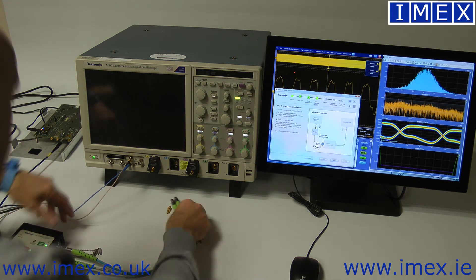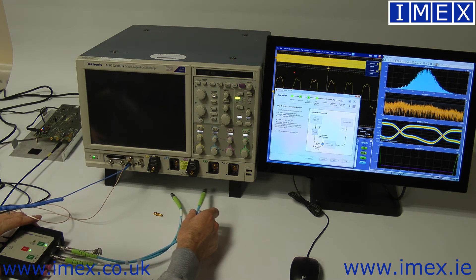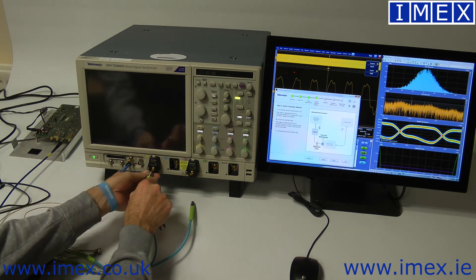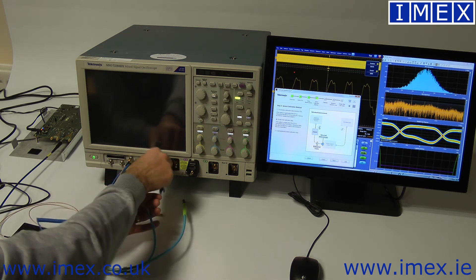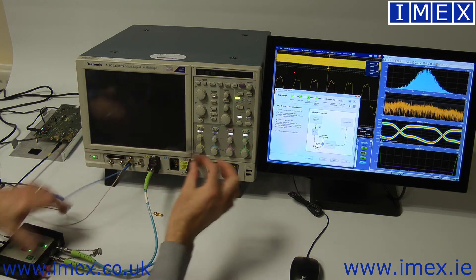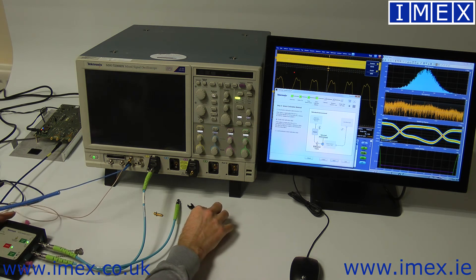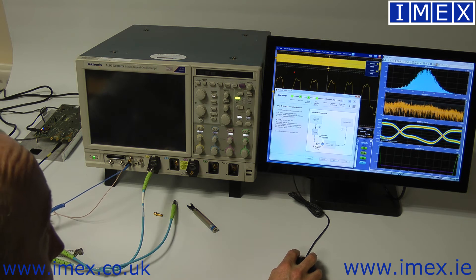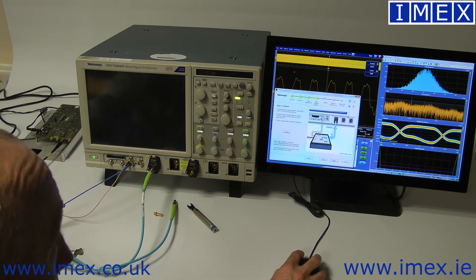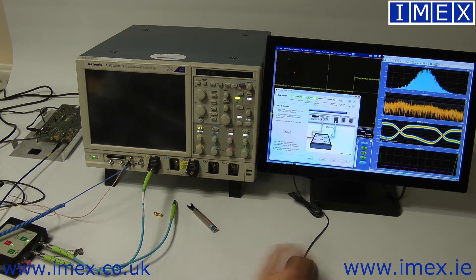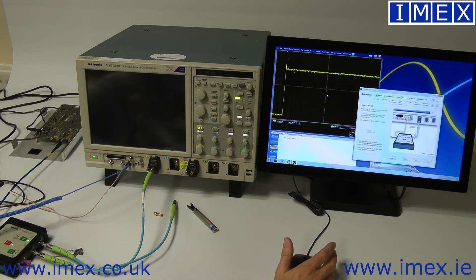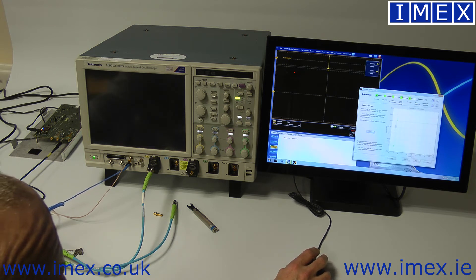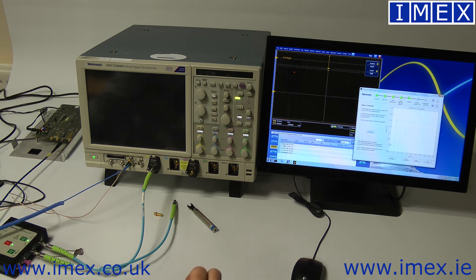Point of note: the equipment is static sensitive so we should have our little wrist strap on. We're working at high frequencies so we want to torque the SMAs in a consistent fashion. We're going to create new calibration data. I've just connected it up here, so just press acquire. The instrument has now gone off — it's using fast acquire mode to capture 40,000 waveforms, basically looking for that 7 picosecond fast edge. Once it's done that, it's now got calibration data. We could save that calibration data for future use.